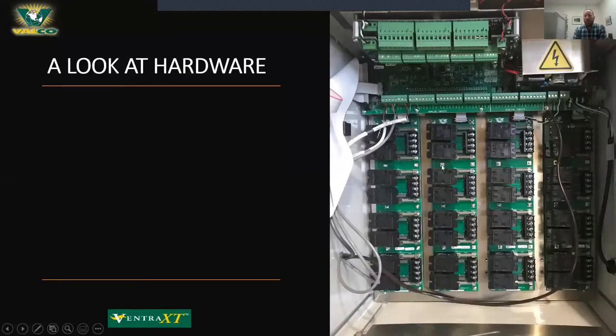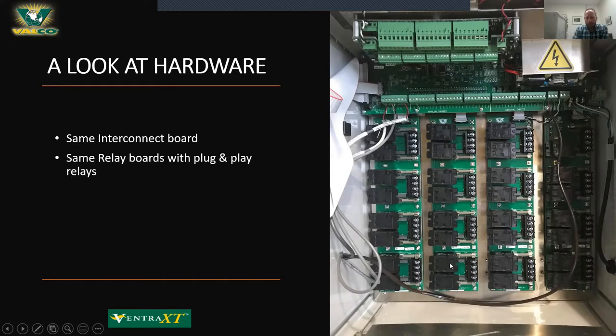Opening the box and looking inside, there's a backboard — the interconnect board — that ties everything together between the front, the back, the relays, and the add-ons. That is the same board. There have been multiple versions over time, but the same version of interconnect board present in the XT is the exact same one in the current versions of the Ventra Pro. The relay boards with individual plug-and-play relays, individual fuses, snubbers, double-pole outputs, and ribbon cable connections are also the same.